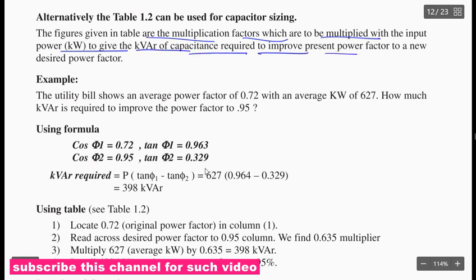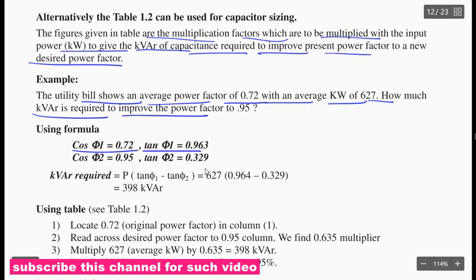Alternatively, a table can be used for capacitor sizing. The figures given in the table are multiplication factors which are multiplied with the input power to give the kVAr of capacitance required to improve the present power factor to the new desired power factor. The utility bill shows an average power factor of 0.72 with an average kilowatt of 627. How much kVAr is required to improve the power factor to 0.95? That is cos phi 1 is 0.72, tan phi 1 is 0.963, cos phi 2 is 0.95, and tan phi 2 is 0.329.